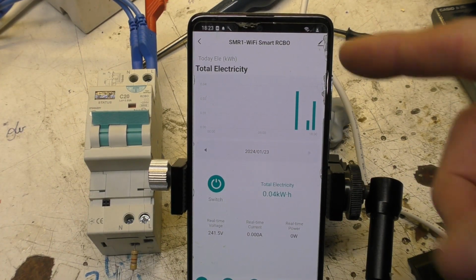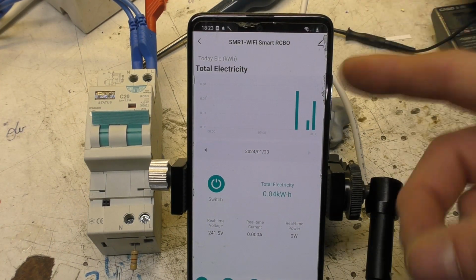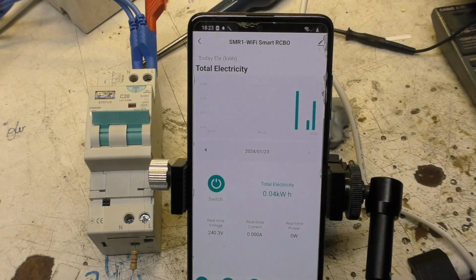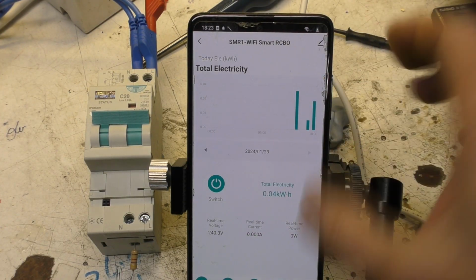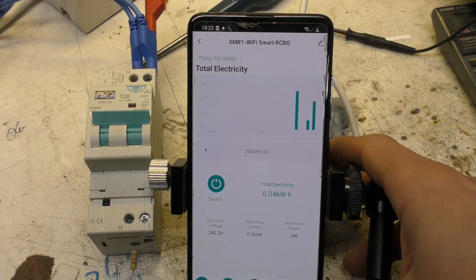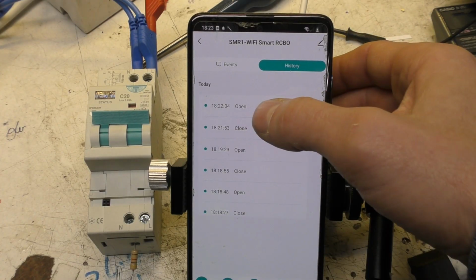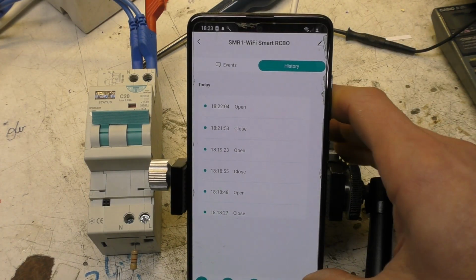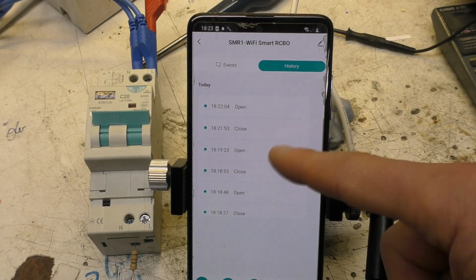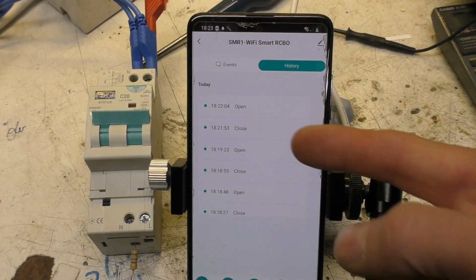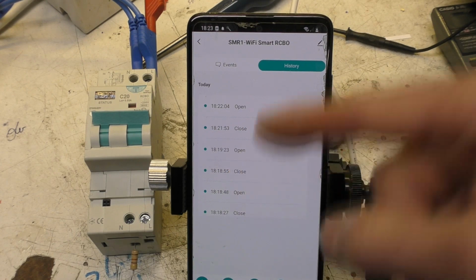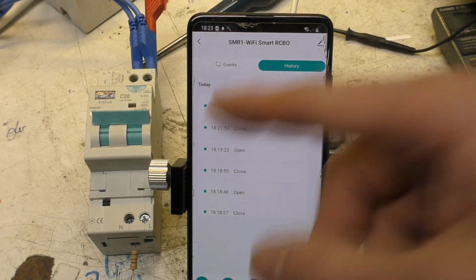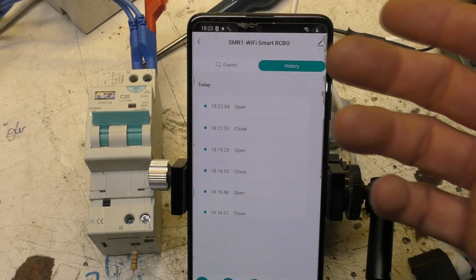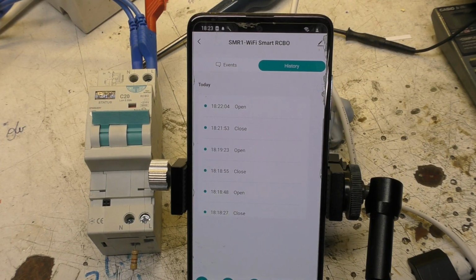When I first installed this, it was generating an alert every time I turned it on and off, but it seems to have stopped doing that. I'm not quite sure why. But we do have some history information, so we have timestamps, but all it says is open, close, overcurrent events. It does actually show the overcurrent as an event, but it doesn't tell you the current. Also, it doesn't discriminate between a manual open or close versus an RCD trip. So this history information isn't hugely useful, or certainly not as useful as it could be.